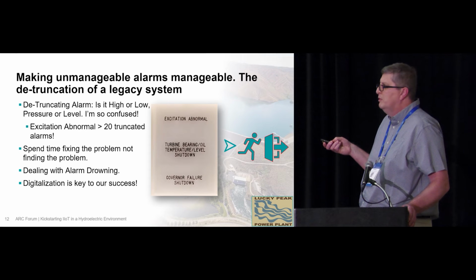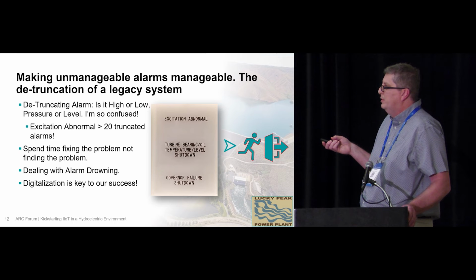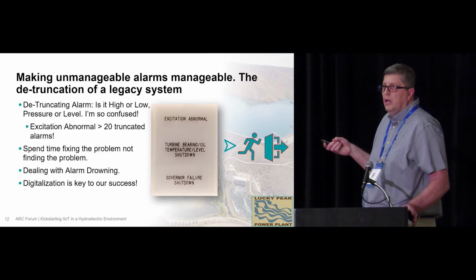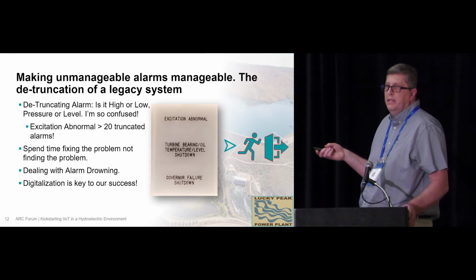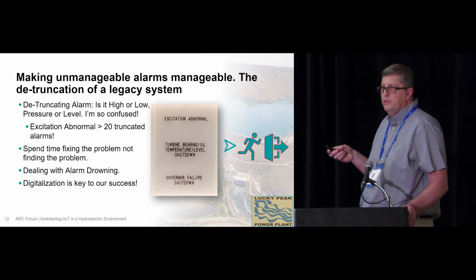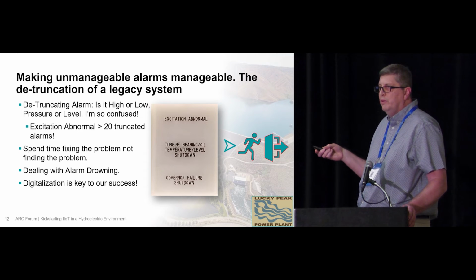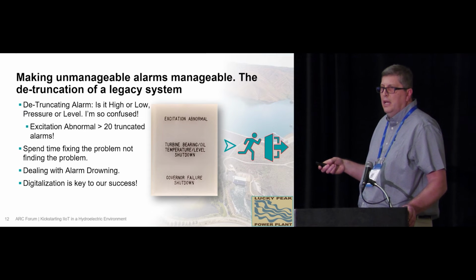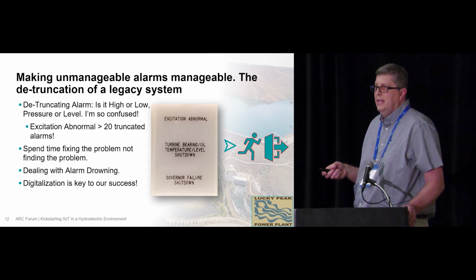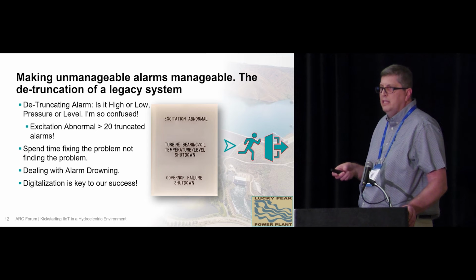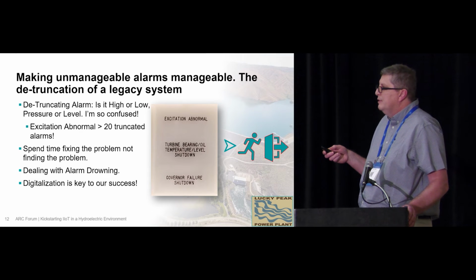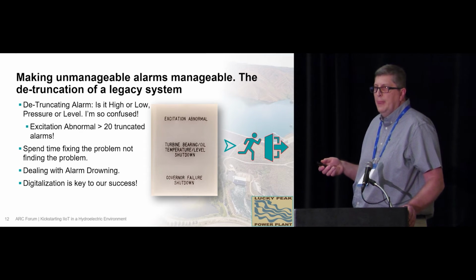Along with our excitation abnormal, we had 20 different alarms that could come in, and they would just light up that one light box to tell you that you have an issue. That makes it really hard to troubleshoot - where do I go look for that? Is it all on the same level? Is it the same piece of equipment? Even our documentation didn't tell us that, so a lot of time was spent figuring out the actual problem and how to fix it.